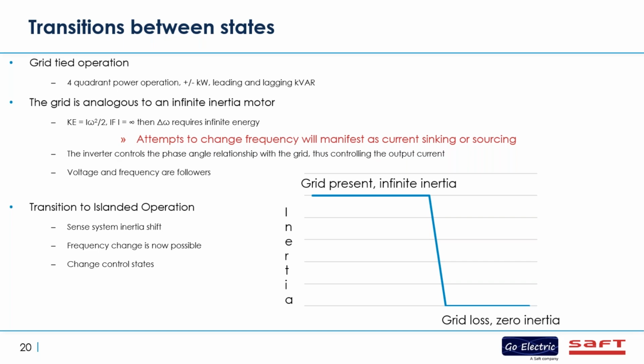So if kinetic energy is related to inertia times the frequency, if the inertia is infinite, then changing the frequency requires infinite energy. And attempts to change that frequency will manifest as current sinking or sourcing. The harder you push or pull on the grid, the more current it takes. The inverter controls the phase angle relationship with the grid, and that controls the primary output current. Voltage and frequency are followers. So the grid is leading and in charge. We are a grid-tied system at this point.